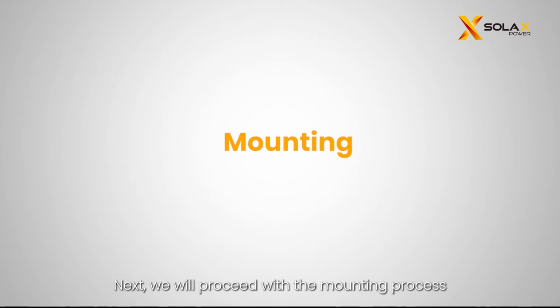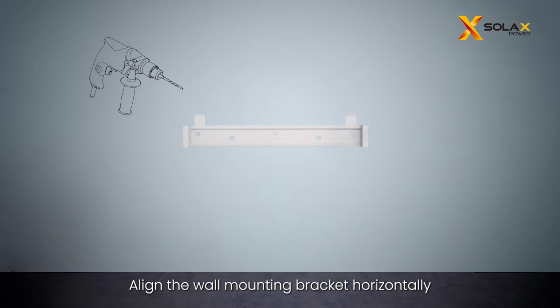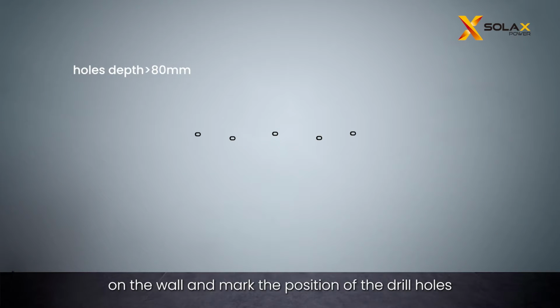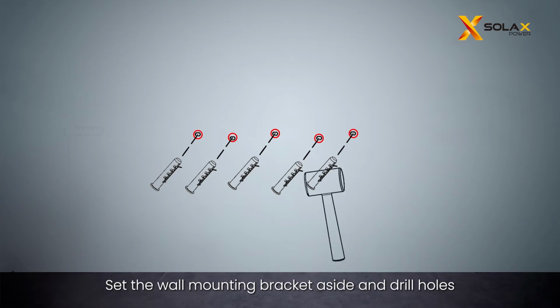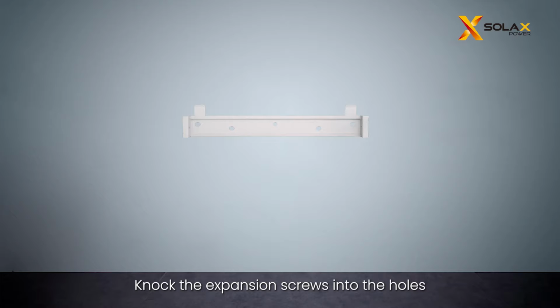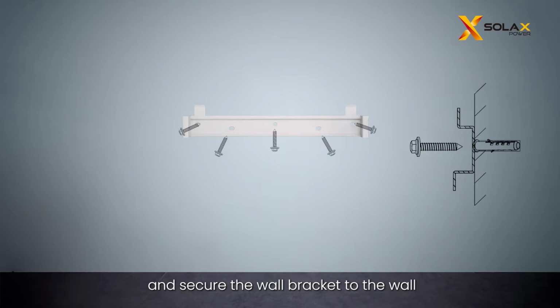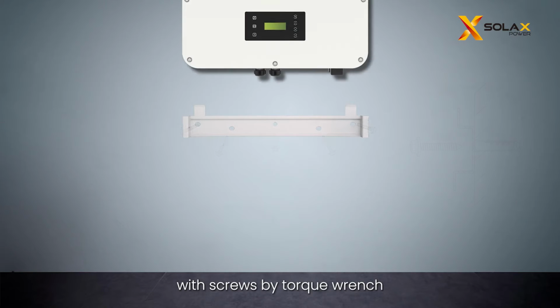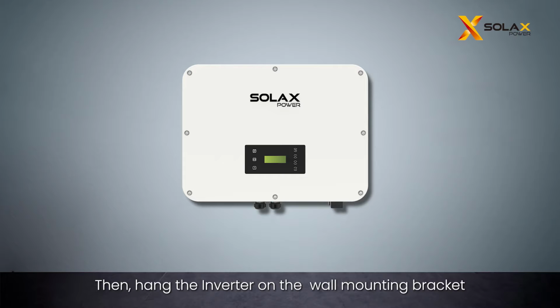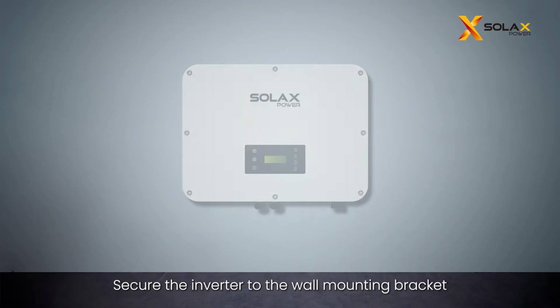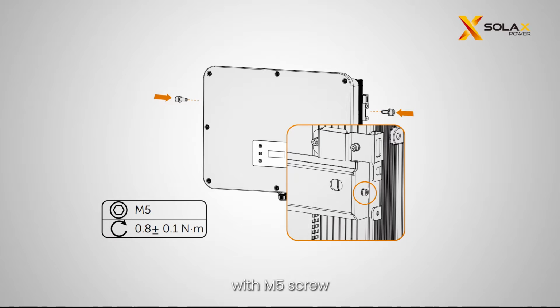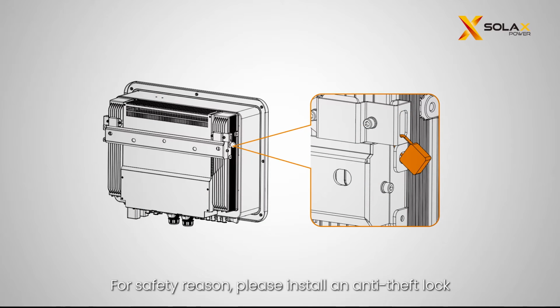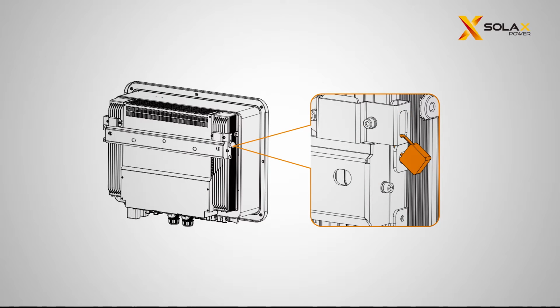Next, we will proceed with the mounting process. Align the wall mounting bracket horizontally on the wall and mark the position of the drill holes. Set the wall mounting bracket aside and drill holes. Knock the expansion screws into the holes and secure the wall bracket to the wall with screws by torque wrench. Then, hang the inverter on the wall mounting bracket. Secure the inverter to the wall mounting bracket with M5 screw. For safety reason, please install an anti-theft lock.